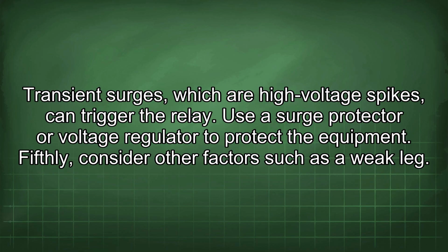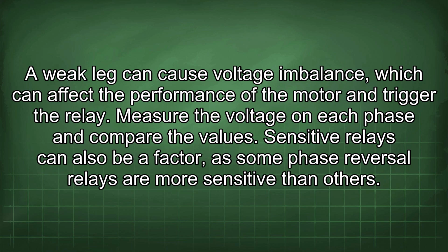Transient surges, which are high voltage spikes, can trigger the relay. Use a surge protector or voltage regulator to protect the equipment. Fifthly, consider other factors such as a weak leg. A weak leg can cause voltage imbalance, which can affect the performance of the motor and trigger the relay. Measure the voltage on each phase and compare the values.